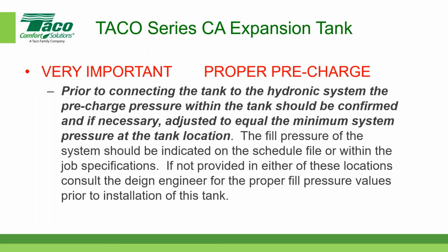You can read this paragraph, I don't have to read it word for word—that's not the type of presenter I am. But we send it out at a 12 psi pre-charge, because we can go a little higher over the road, but trucking laws only let us go so high. Rich has talked about how you determine the minimum fill pressure needed for that pre-charge, and it has to be adjusted prior to connecting the tank to the hydronic system.